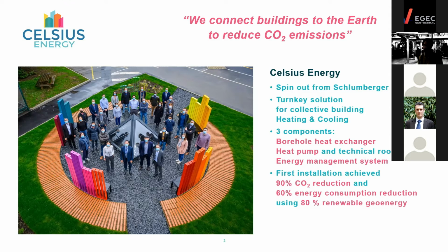Schlumberger building near Paris, in Clamart, south of the city. And it has already achieved a reduction of a factor of 10 in CO2 emissions in comparison with the previous gas-fired heating system and electrical cooling system. And even the consumption of energy has been reduced by more than half. And all this with 80% of the time, the energy to the system was coming from the renewable source, from the geothermal heat pump.